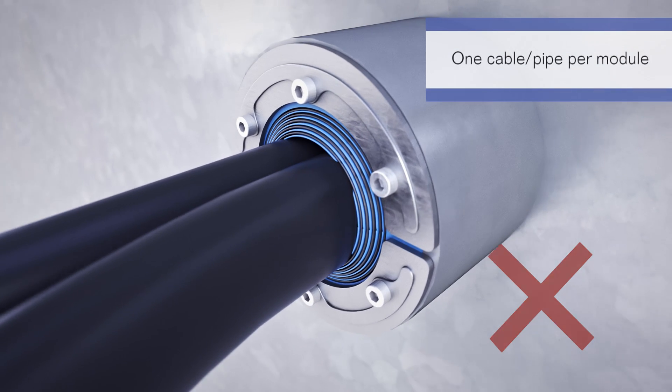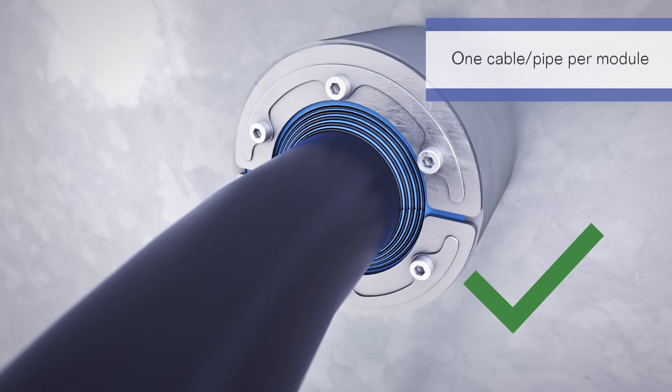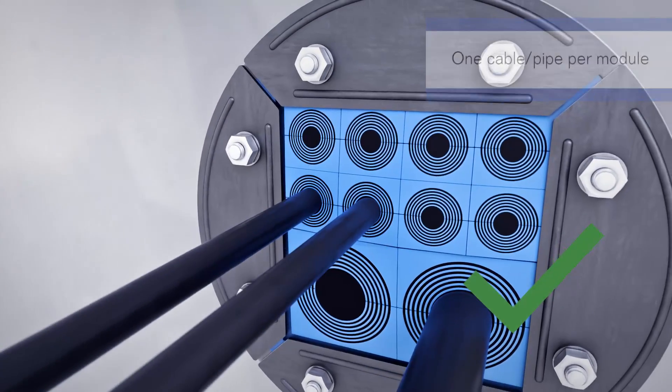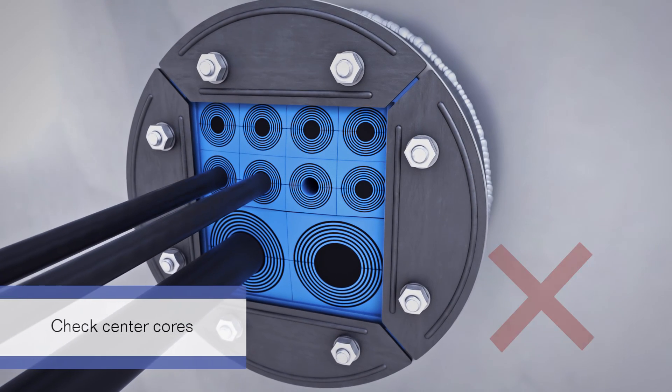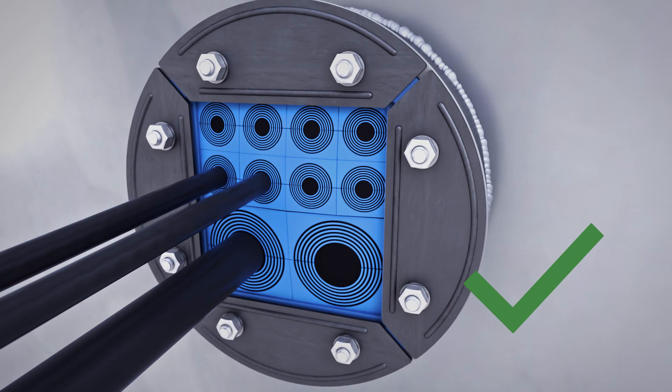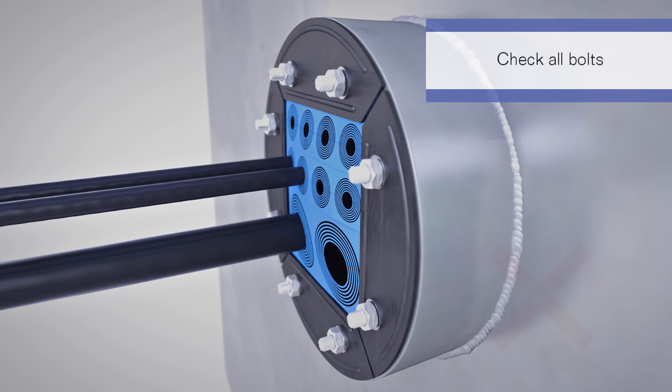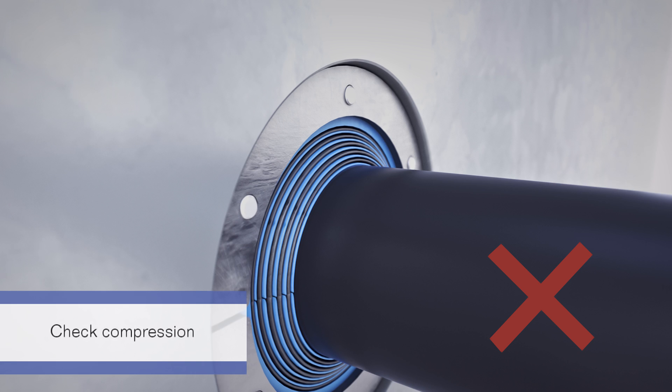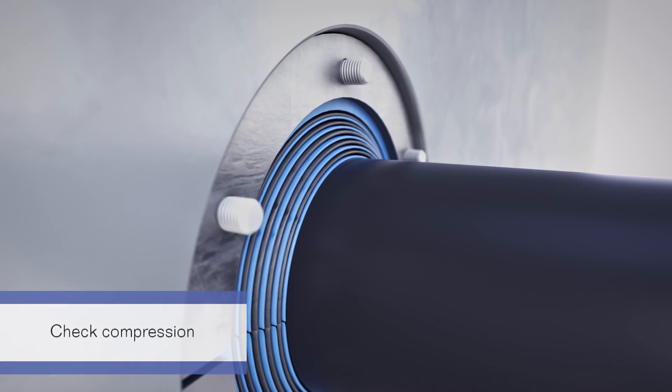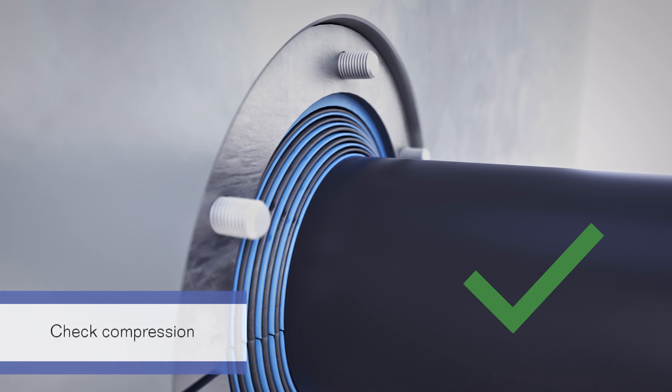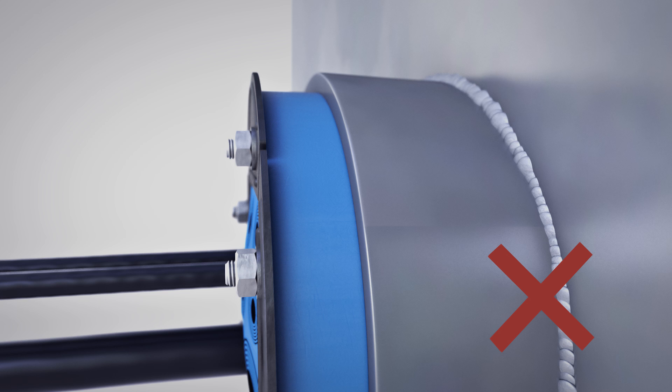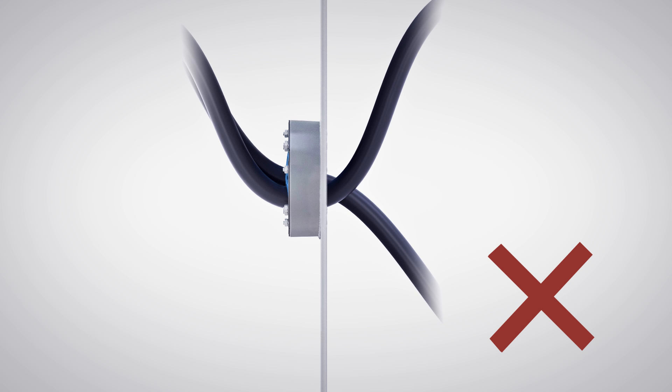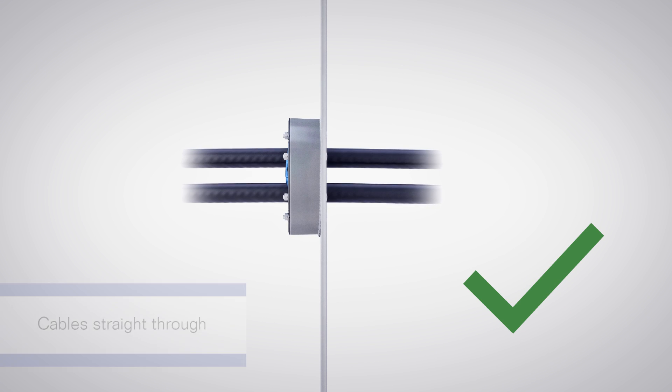Make sure that multiple cables or pipes don't pass through the same module slot. Check that there are no center cores missing. Check that all bolts are tightened in a similar way. Verify that the frame is pushed all the way into the sleeve. Make sure that the cables go straight through the frame.